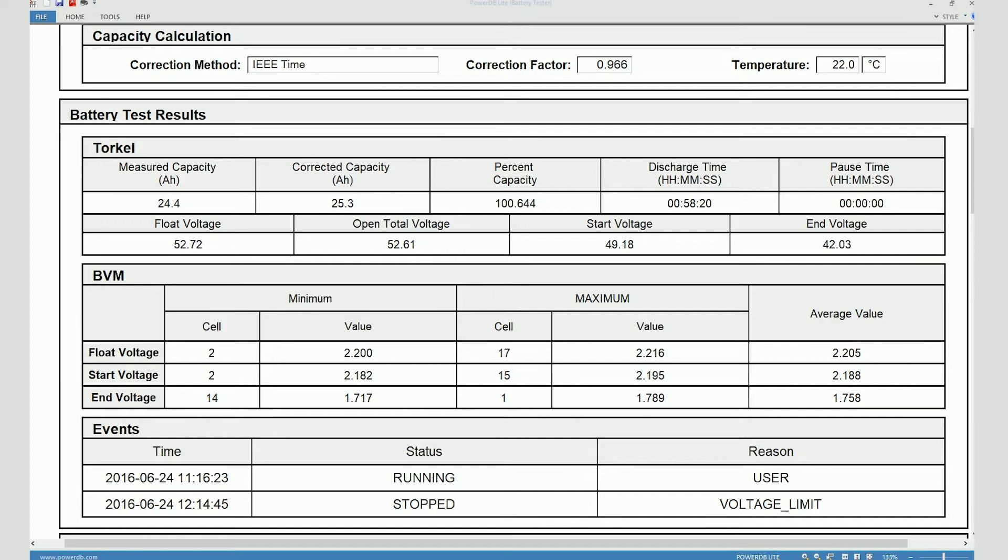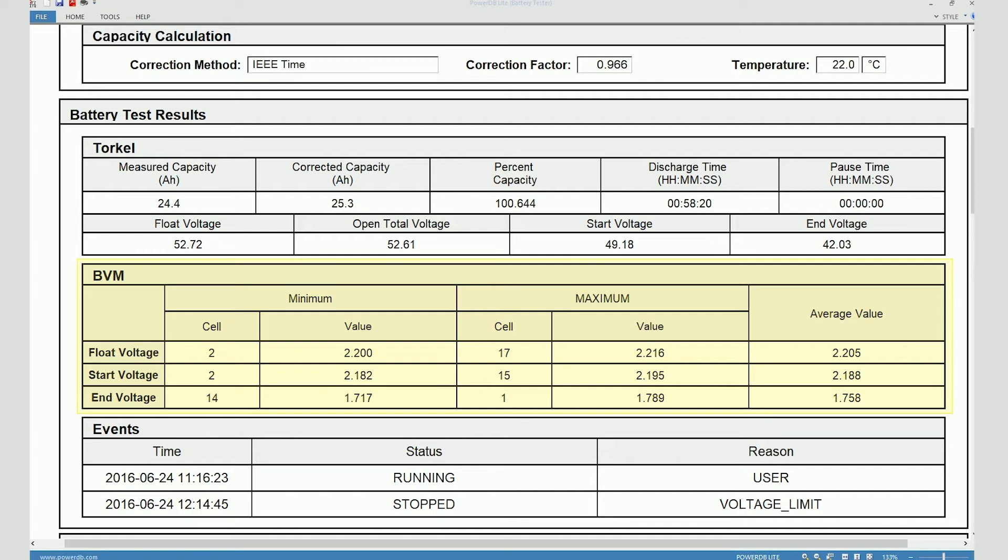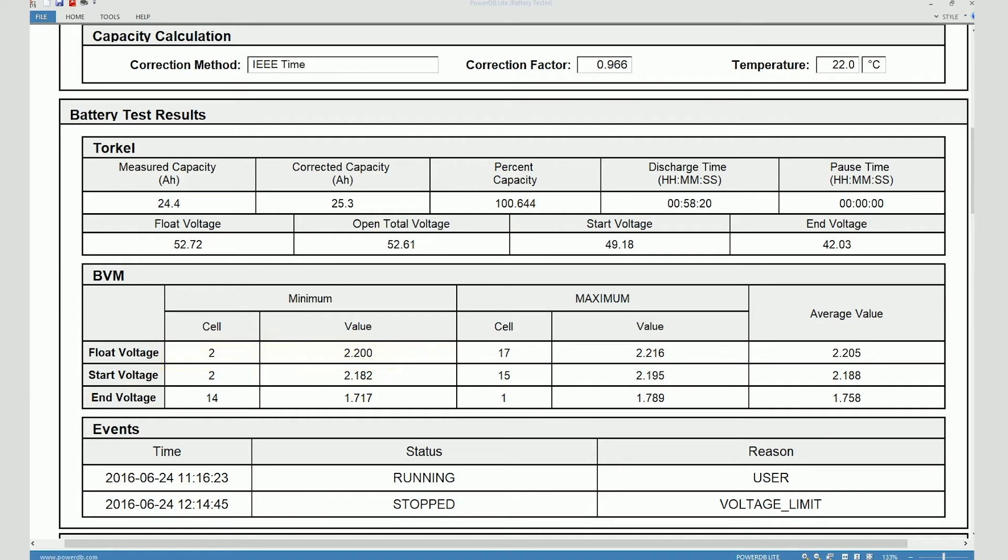Then you can see a summary of the individual cell voltage data which is measured by the BVMs. So you can see the minima and the maxima observed on various cells for the float voltage and start voltage and the end voltage. As an example, if you want to talk about float voltage, the minimum float voltage value was recorded on cell number 2 and the value that was recorded was 2.2. Similarly, the maximum float voltage value was recorded on cell number 17 and the value that was recorded was 2.216. The average values for all these parameters are also provided in the last column.